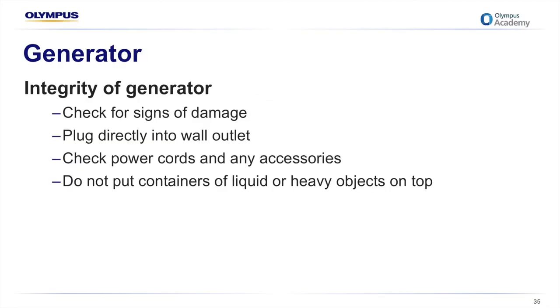The generator should be checked for any signs of damage. If there's any question about the integrity of the generator, it should be checked by a biomedical engineer. Generators should be plugged directly into a wall outlet and not into a power strip or extension cord. The power cord should be checked to make sure it's not frayed or damaged. Any other accessories that are attached to the generator should also be checked. Instructions for use that accompany the device will provide more specific information.